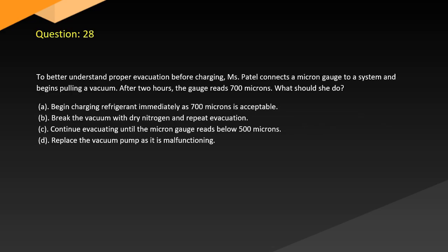Question 28. To better understand proper evacuation before charging, Patel connects a micron gauge to a system and begins pulling a vacuum. After 2 hours, the gauge reads 700 microns. What should she do?